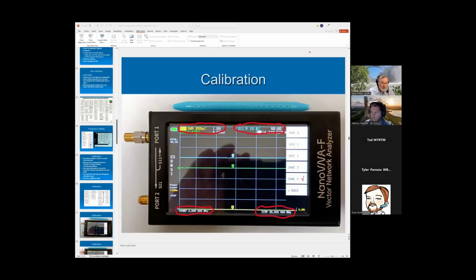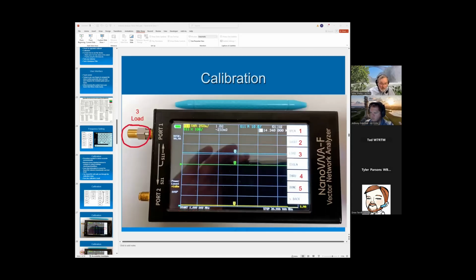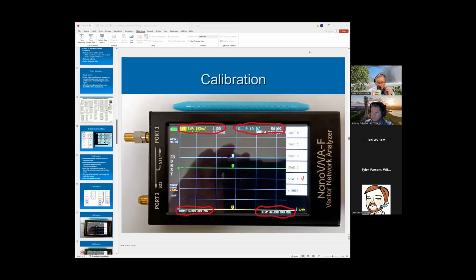Okay, here we go. This one basically takes you through the steps. When you're doing your calibration, on the right hand side you can see it shows open, short, load. As you go through each one of those steps, it will gray itself out, saying that you've already done that particular calibration. So it'll confirm what you have there. Then when you get all finished, you hit done and go off and save what you've done. This one I've already talked about.